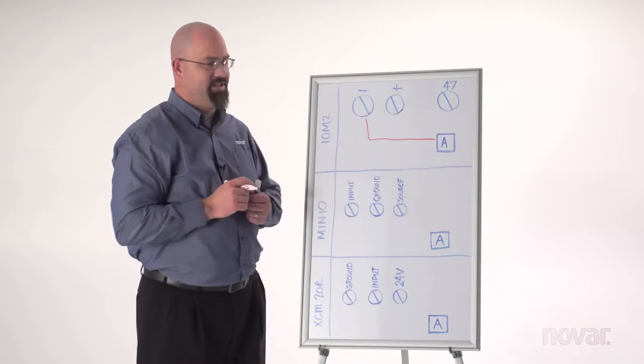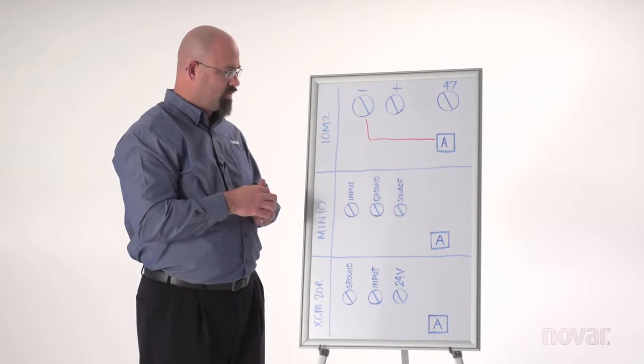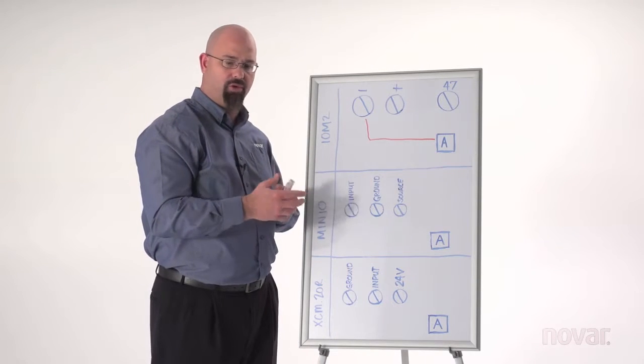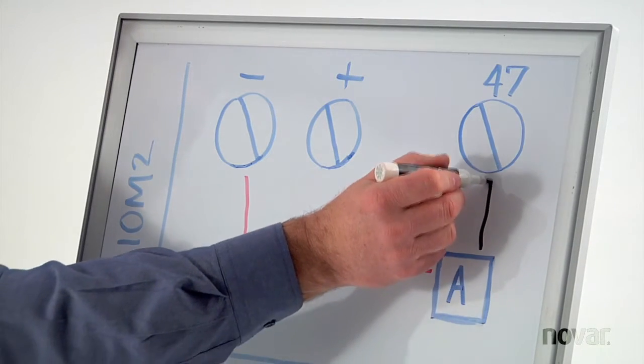Now this is a DC signal, so we need to have a reference on this DC signal. So from that sensor, we'll have a GND or a ground or a common terminal, and we're going to connect that to the IOM-2's terminal 47.